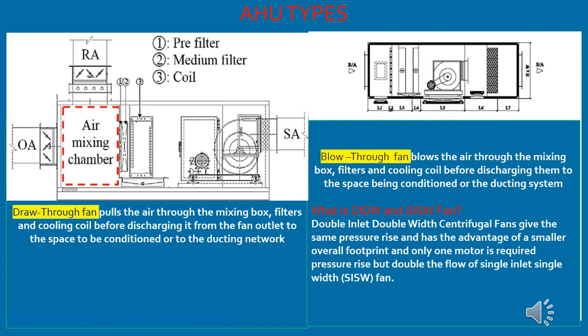In the types of AHU, we are seeing only the general type here — detail on EC fan and plug fan will be covered in the next video. There are two types of fan arrangement: draw-through fan and blow-through fan. A draw-through fan pulls the air through the mixing box, filters, and cooling coil before discharging it from the fan outlet. A blow-through fan blows the air through the mixing box, filter, and cooling coil before discharging it to the space.